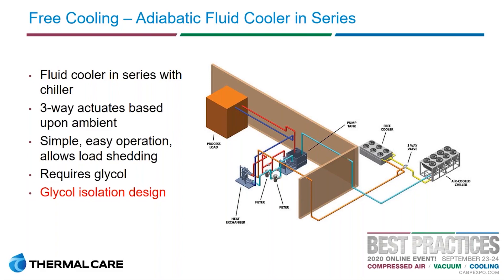That way, we can still run the pieces of equipment sitting outside and exposed to ambient conditions without having to worry about glycol inside the facility going into the machines. One key thing to note is that the pump tank depicted — with the red lines, light blue, and orange going into it — is a fully divided tank. The tank on the left and the tank on the right are two completely separated wells: one is 100% water and the other has a glycol mixture. This allows one large tank with two independent wells, reducing footprint and cost since you don't have to buy two separate tanks.